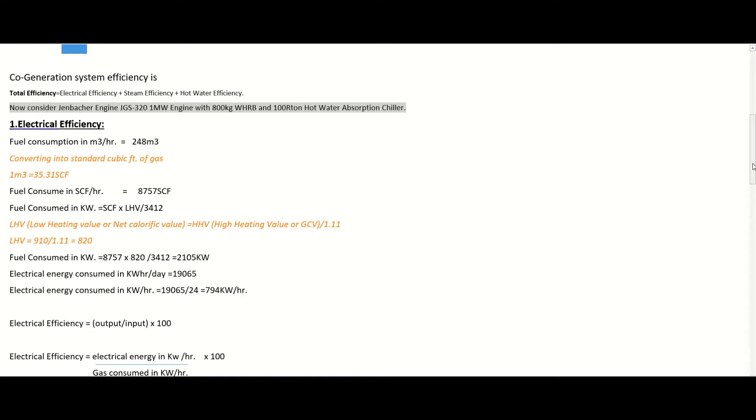Now consider the system I am personally running: a GE Jenbacher gas engine JGS 320, 1 megawatt. I am running an 800 kg waste heat recovery boiler on the JGS 320 exhaust, and also running a 100-ton hot water absorption chiller. Let's calculate the efficiency of my system — you can calculate the efficiency of your own system by changing the required parameters.